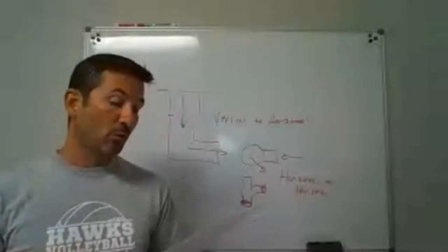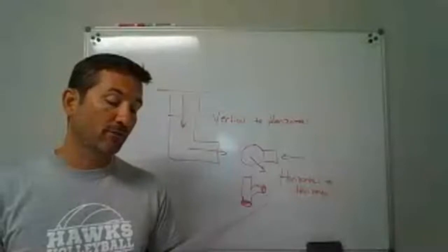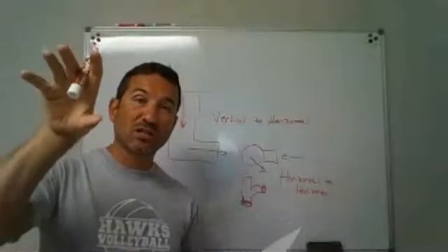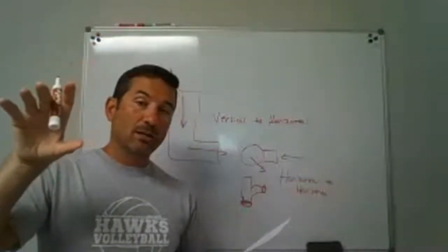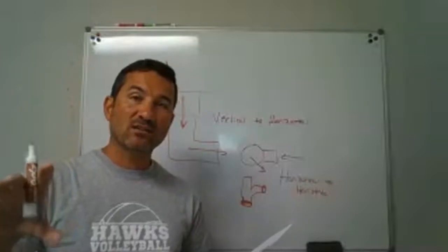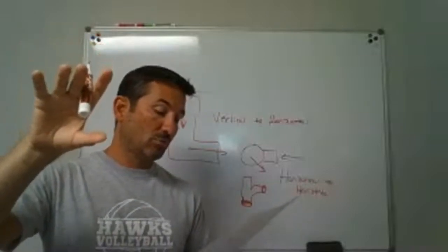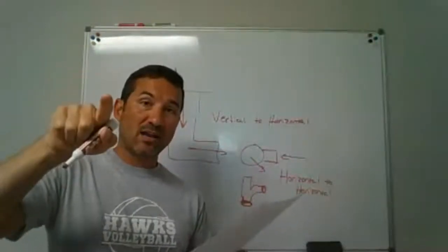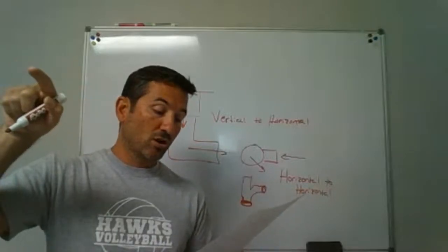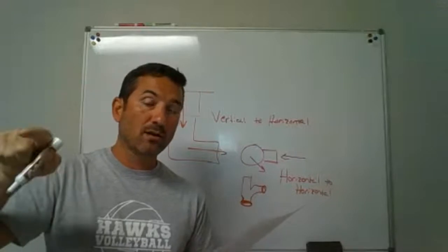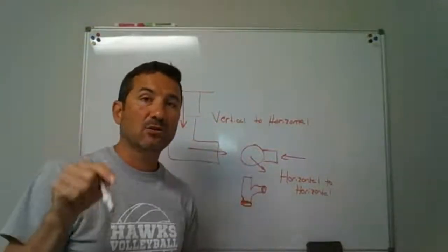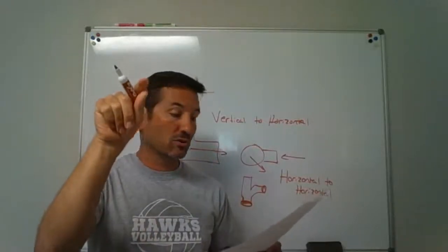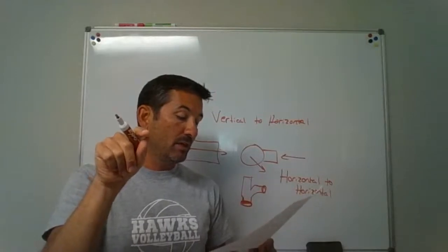maximum DFUs on a 4-inch building drain with a 1/4 inch per foot slope. Okay, that was that first chart, sizing building drains, building sewers, that we were covering there. Don't go down to the horizontal drains and stacks. That was the lower one. The upper one's building drain is what we're calling it. And now find 4-inch over on the side. Trace it over to the column that has 1/4 inch per foot slope on it. Where the two meet, that's going to tell you how many DFUs you can have on there. So you got a 4-inch drain, trace it across to the 1/4 inch per foot column, and it will tell you how many DFUs.